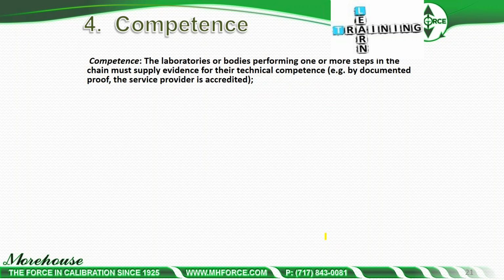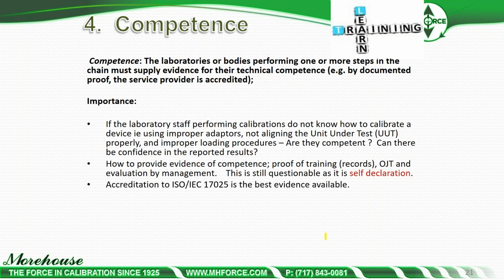So the next step is competence. The laboratories or bodies performing one or more steps in the chain must supply evidence for their technical competence. This is by documented proof. The service provider is accredited. The importance of this: if the laboratory staff performing calibrations do not know how to calibrate a device, i.e. using improper adapters, not aligning the unit under test properly, and improper loading procedures, are they competent?